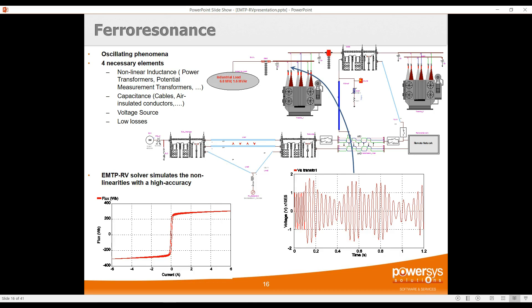Ferroresonance can occur when there is a nonlinear inductance — typically from a transformer, voltage transformer, or reactor — in series with a capacitance. It can occur in situations such as a breaker failure, or when disconnecting a VT with the grading capacitance of a breaker in series. EMTP can simulate this, and in a lot of detail — reproducing the hysteresis and saturation curve of the transformer — allowing identification of all types of ferroresonance: periodic, aperiodic, or completely chaotic.